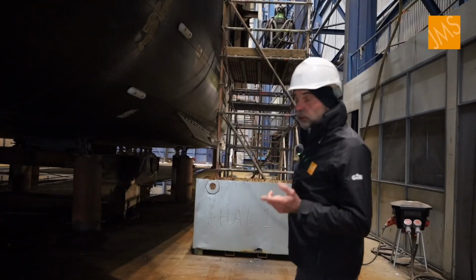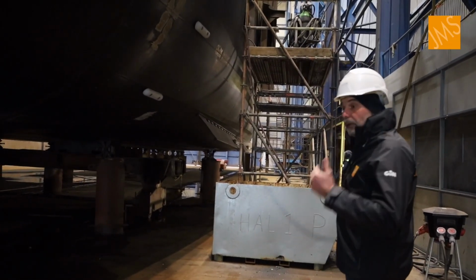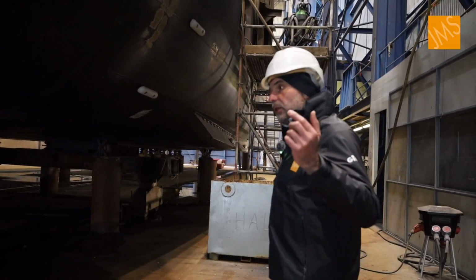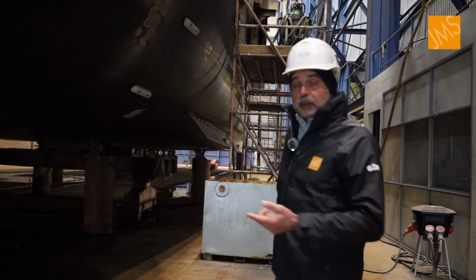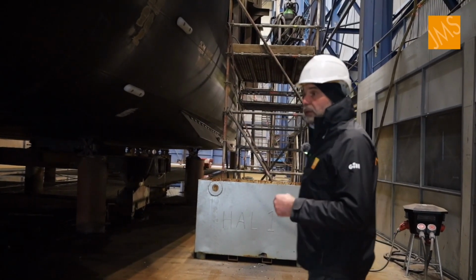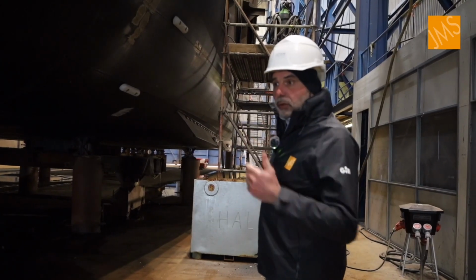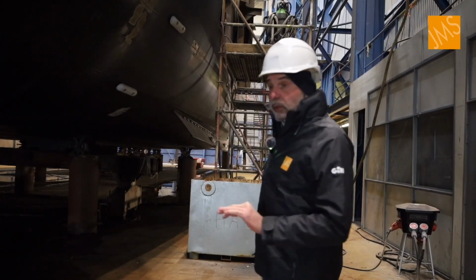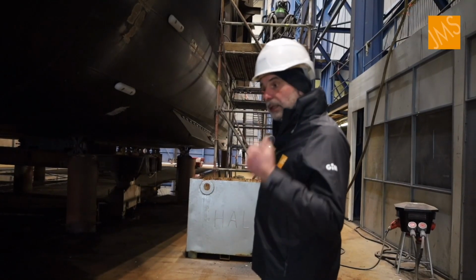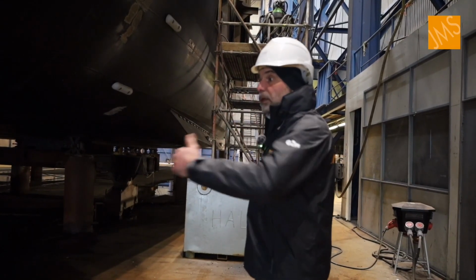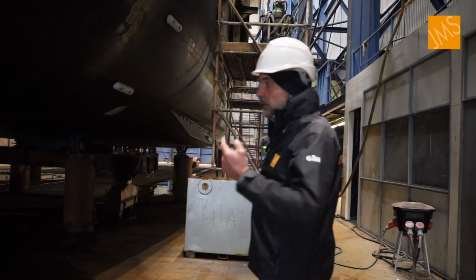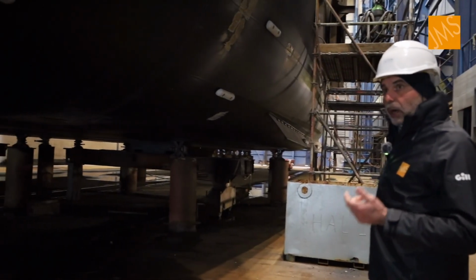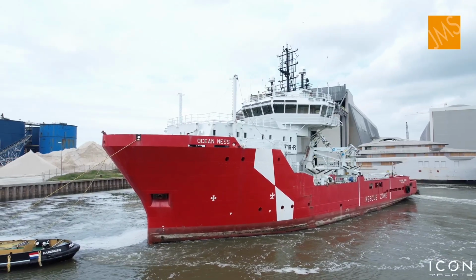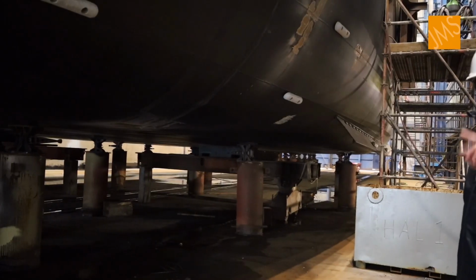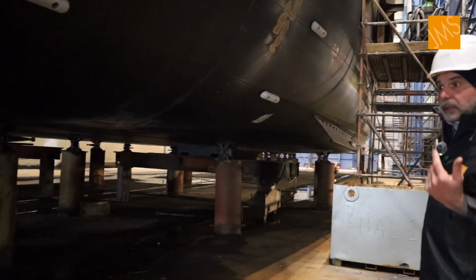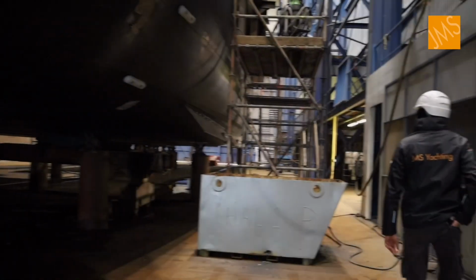It goes to the chiller units and also to big heat exchangers, so that everything on board will be fresh water. Why did we choose for that? On many yachts I see seawater systems, where your engines are cooled with seawater as well, and that always causes big issues. So here there is a freshwater low temperature system looped around all the engines, the thrusters, the switchboards, whatever. The only thing that really needs seawater is the chiller unit, because the temperature difference was not enough with the cool water loop in the engine room.